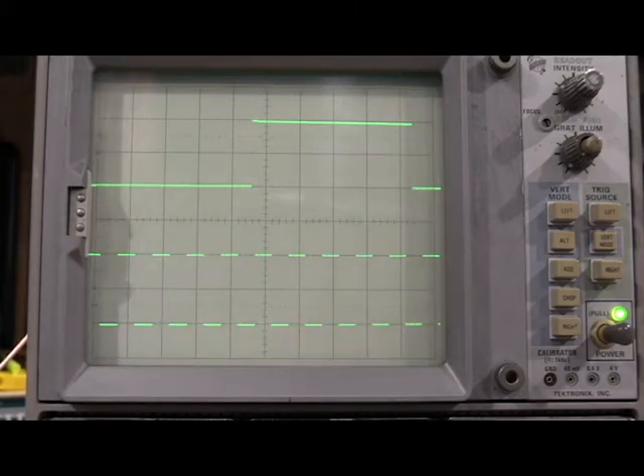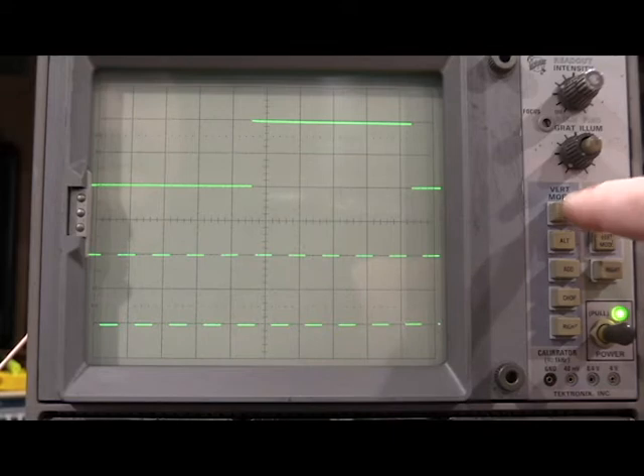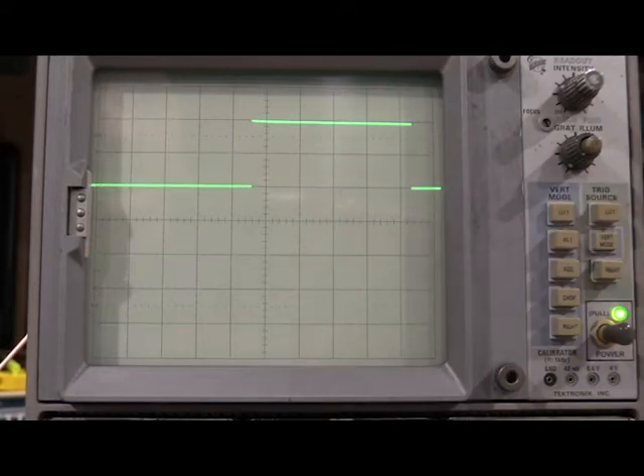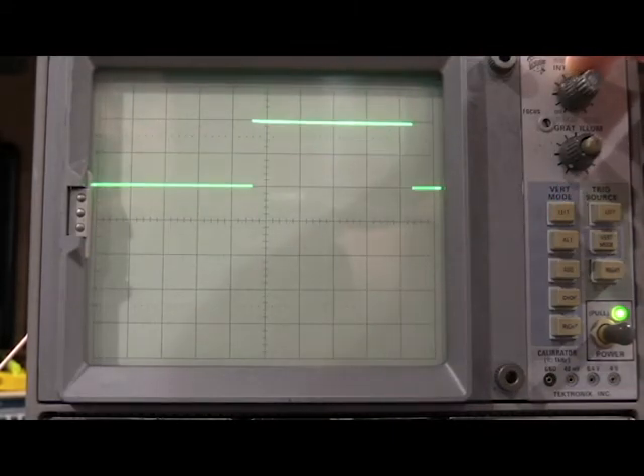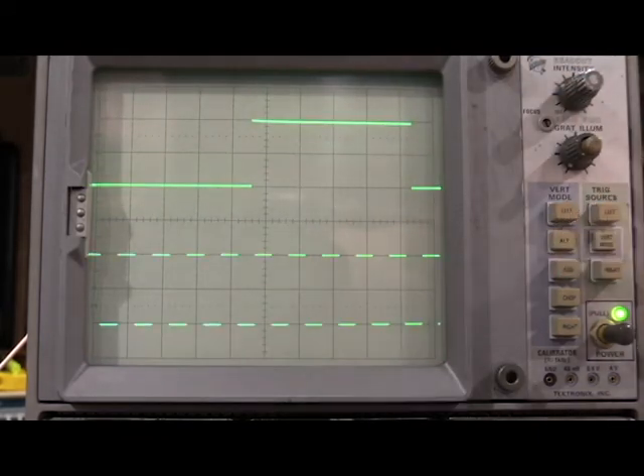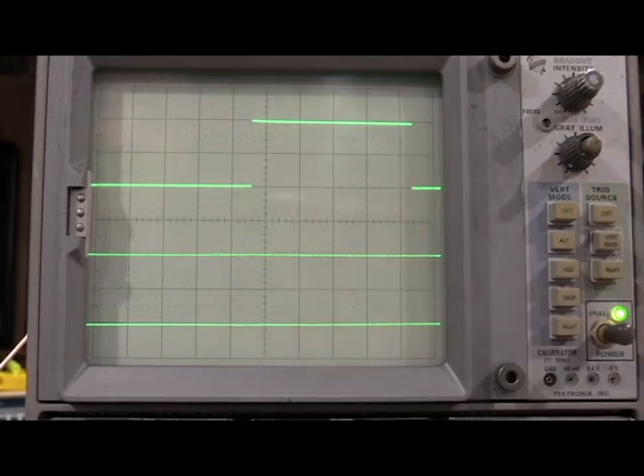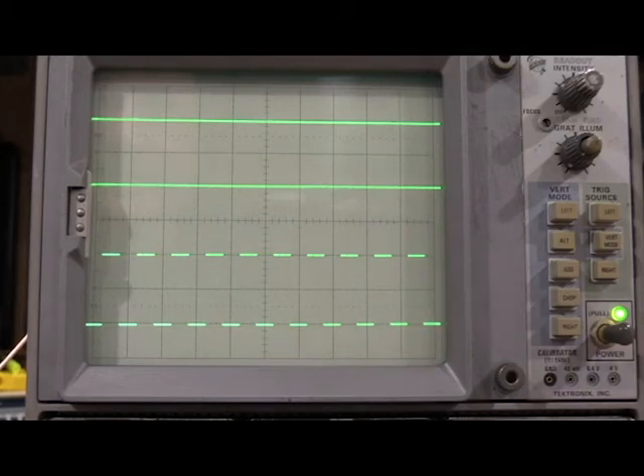And then if I set this to the left, only the top waveform should be stable. Set this to left, top waveform should be stable. This one untriggered. If I set it to right, the bottom one should trigger and the top one should become unstable. And that's it for that test. That's actually all the triggering testing that the service manual requires. So I'm into calibrating the horizontal deflection system next.